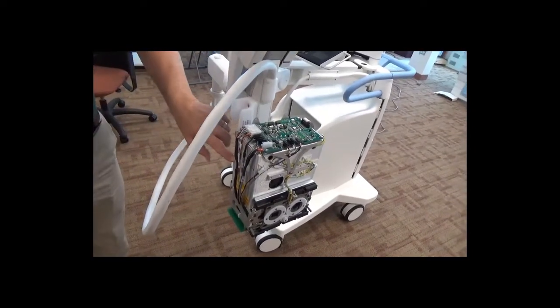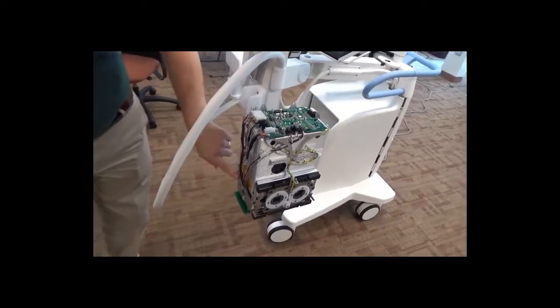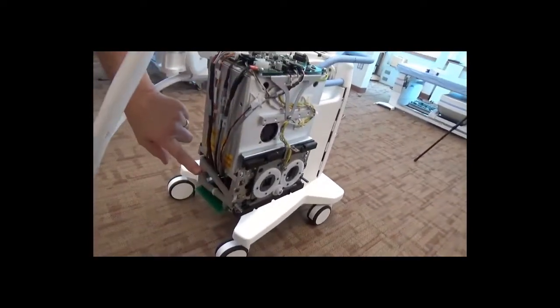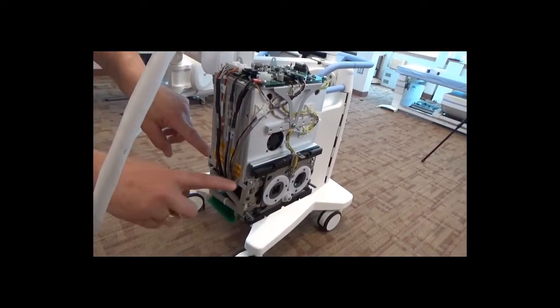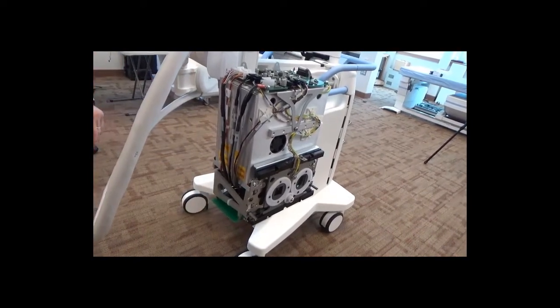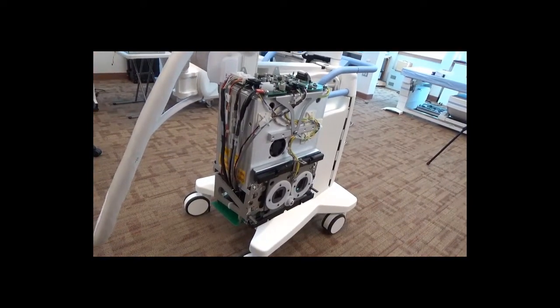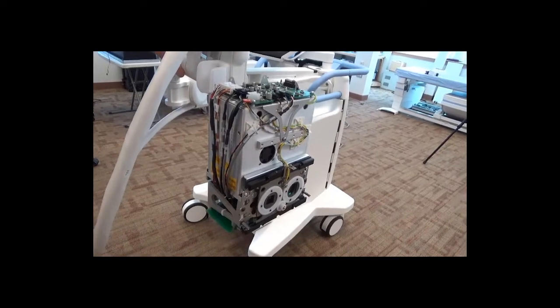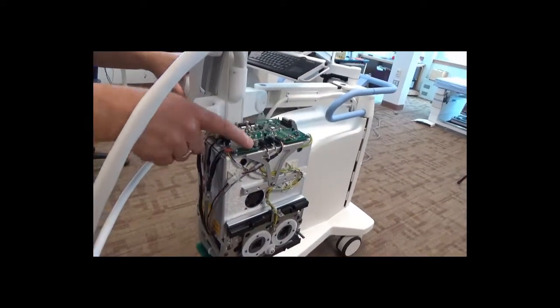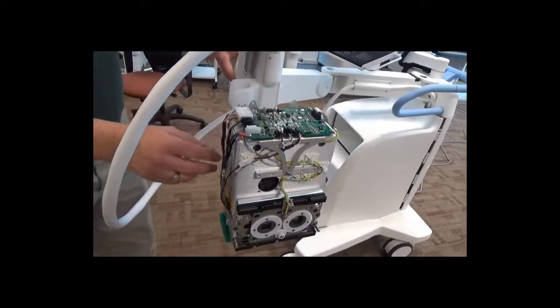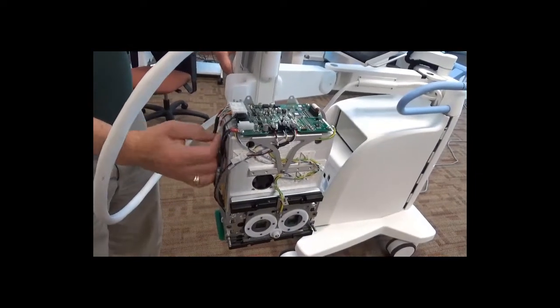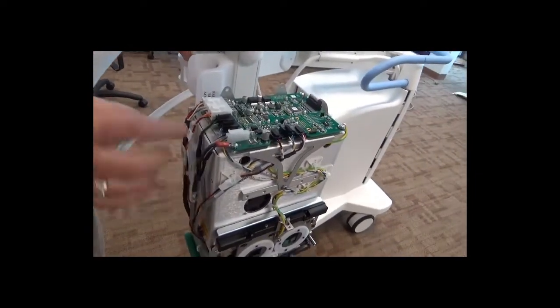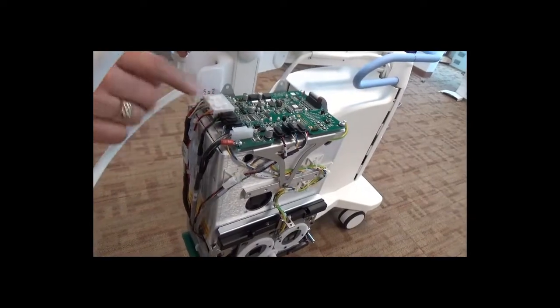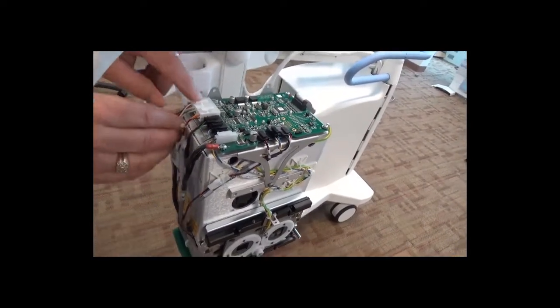The replacement X-ray source is going to come with this bracket, but we're not going to take that bracket off. Instead, we're going to remove the X-ray source using those screws. But we have some work to do before we get to that. And that is we're going to remove all of the connectors to the C-arm board. And as you can see, they're all well marked, and they're pretty much idiot-proof because every connector is different, and they're also keyed.